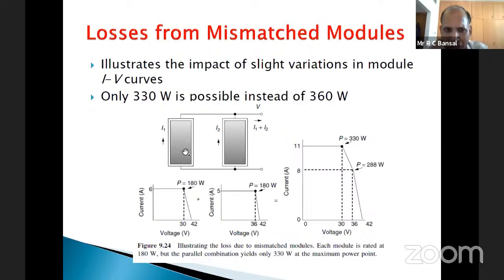Why is this so? One module has a current rating of 6 amps at a rated voltage of 30 volts, the other has 5 amps at a rated voltage of 36 volts. When connected in parallel, the total current contributed will be 6 plus 5, which is 11 amps. But in a parallel circuit, the voltage across both modules will be the same, just 30 volts, not 36. So 30 multiplied by 11 gives a power rating of 330 watt instead of 360 watt.